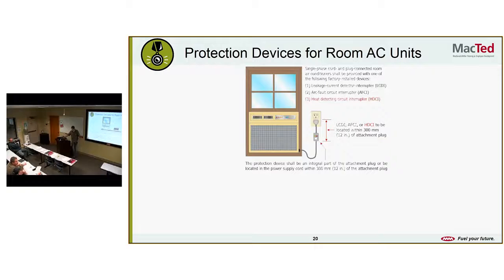All right, protection devices for room AC units, window shakers. Single-phase cord and plug connected room air conditioners shall be provided with one of the following factory installed devices. One, leakage current detection interrupter. That's a new one to me. LCDI. Or an arc fault circuit interrupter. Or a heat detecting circuit interrupter. Anybody ever heard of those ones? Well, now you got to have them on a window shaker. So if it's starting to overload, there's some way for it to cut off. Shall be an integral part of the attachment plug or be located in the power supply cord within 12 inches of the attachment plug. They should be factory installed. Up in the top there. Yeah, factory installed. So be looking for those.